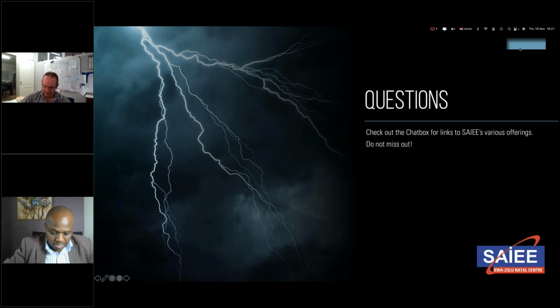For PV systems, using the earthing of those systems as a lightning down conductor is not a good idea. Remembering that it is there, those things are bonded to the chassis of the PV panels. If we want to allow the lightning strike to terminate on the panel, there are many samples of how the edge of the panel has been totally destroyed because of the mechanical energy. We talked about the 200,000 kilojoules, that's what causes the mechanical damage on PV panels. So it's not a good idea. It's more sure if you provide a dedicated, separate path off the panel to the common earth.